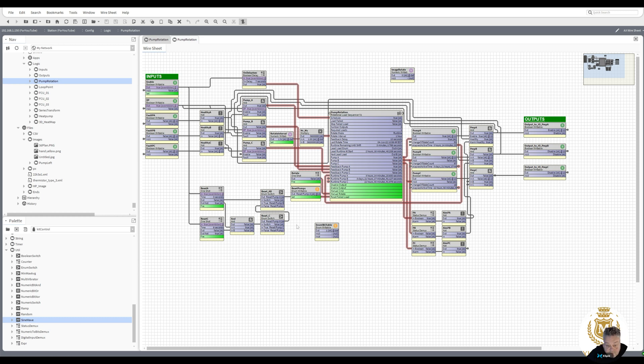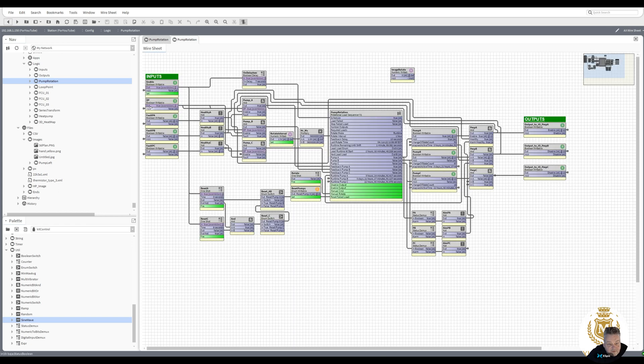I've added the rotational interval — it's just a numeric writable — and then we multiply that by 3,600,000 to give us our milliseconds for the rotational interval. We've set that to one hour. We've got our feedback delay on 10 seconds, and these are our feedbacks from our pumps and our one-times on our pumps. That's our manual rotate.